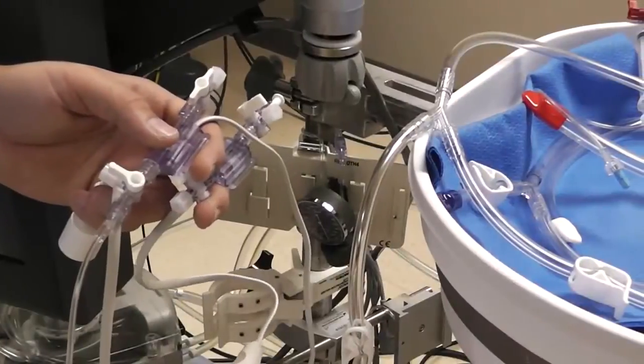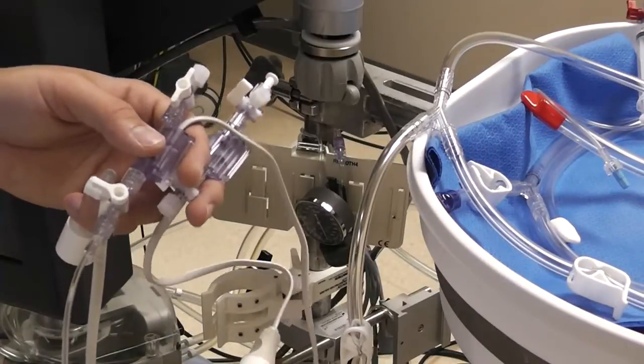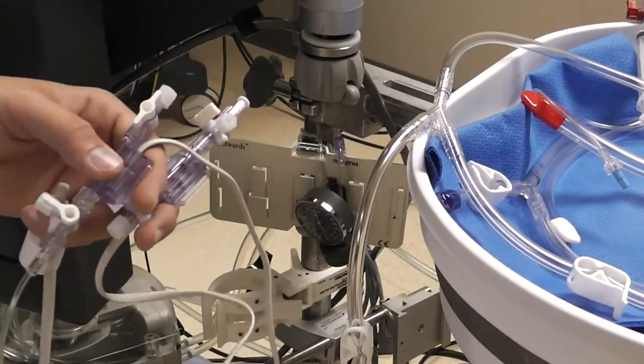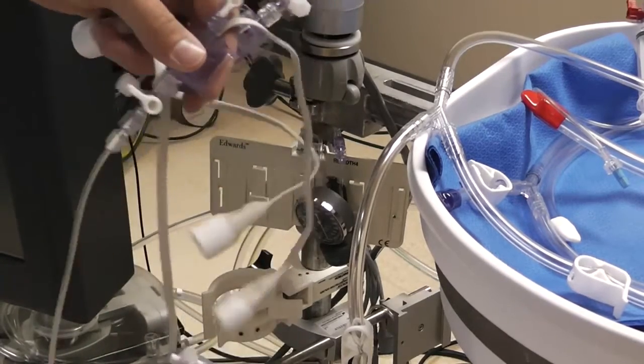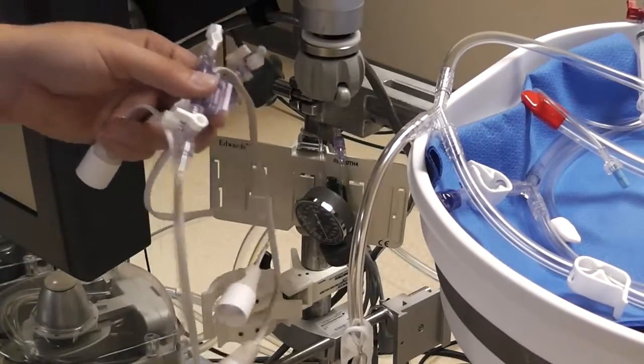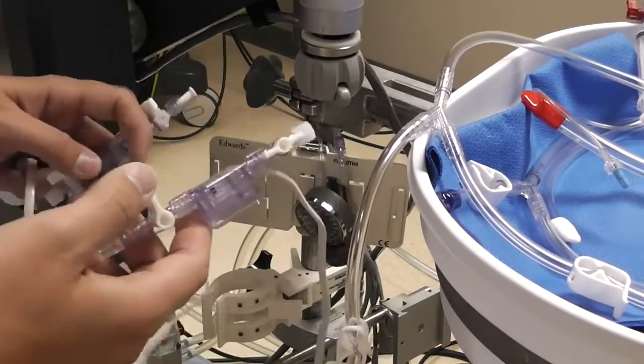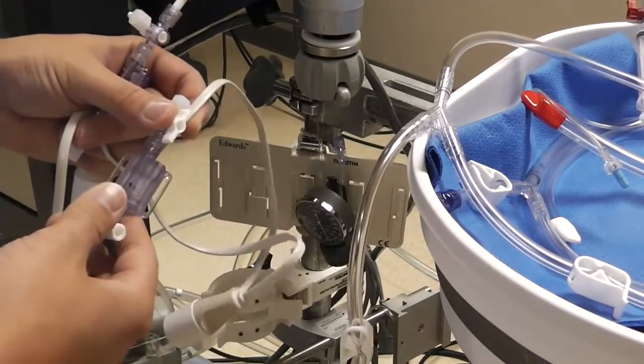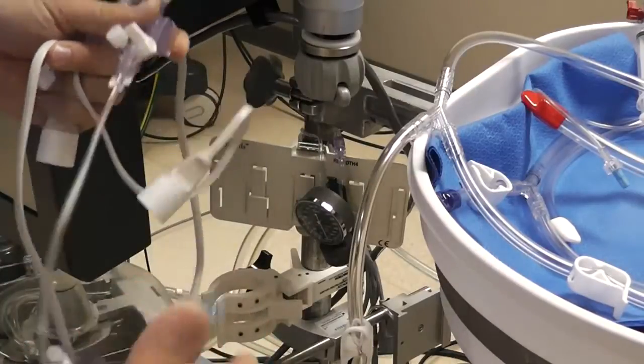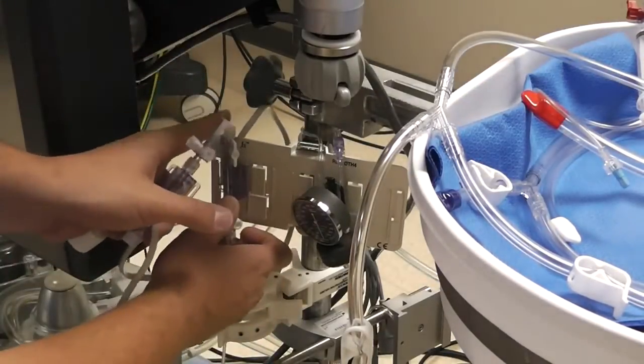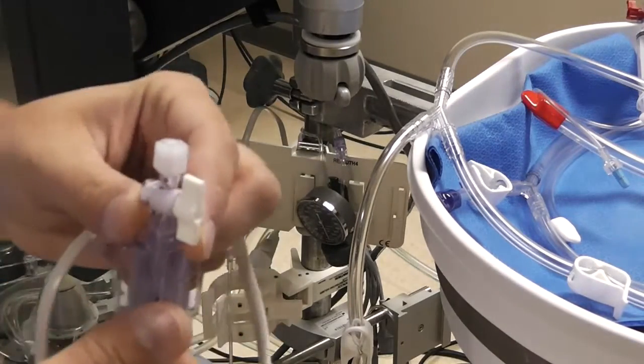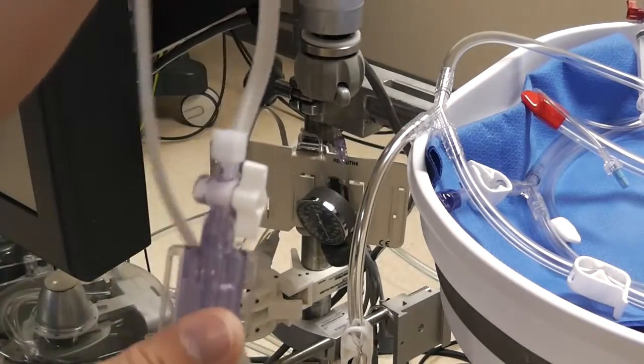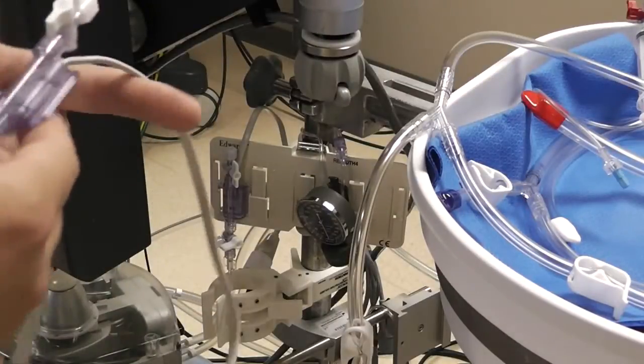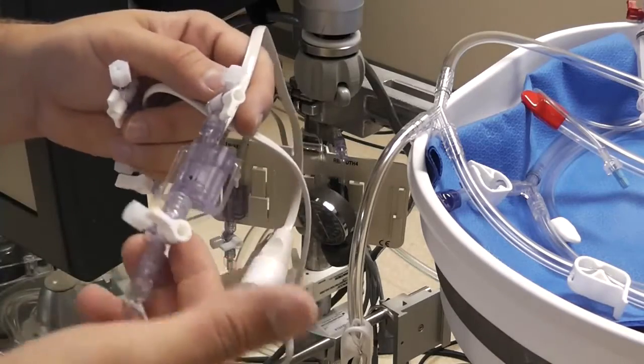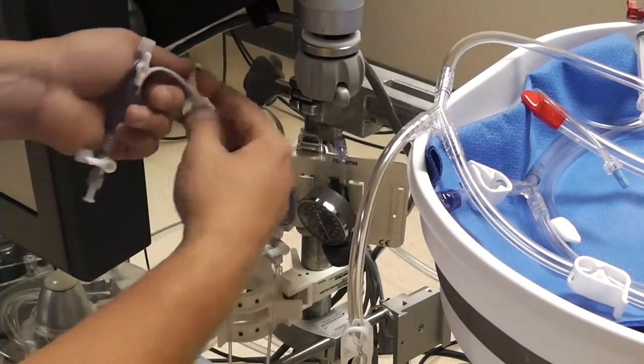Next we're going to mount the pressure transducers, and on this pump run today I'm doing valves, so I will be using retrograde, so there will be 3 pressure transducers. On some cases where you do not have retrograde, you will only have 2. In any case, the 2 you will always have will be the arterial pressure transducer, which does have a line attached to it, and that will go to the far left in this holder with this side up, with the line connection coming out the top. And the next one will be the reservoir pressure, and that will go just to the right of the arterial.